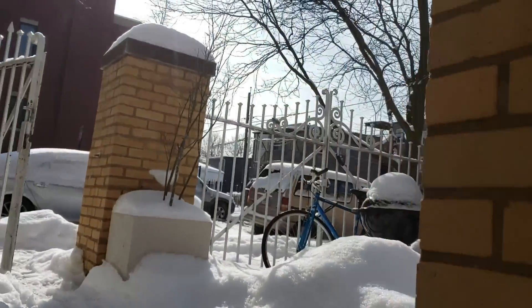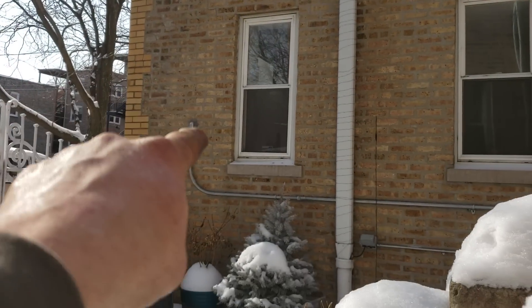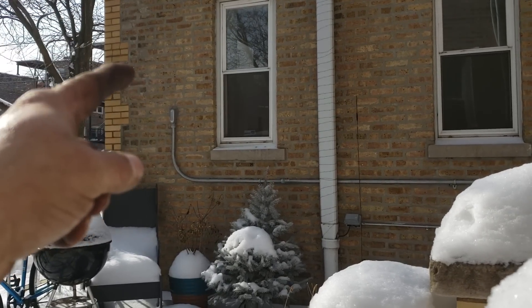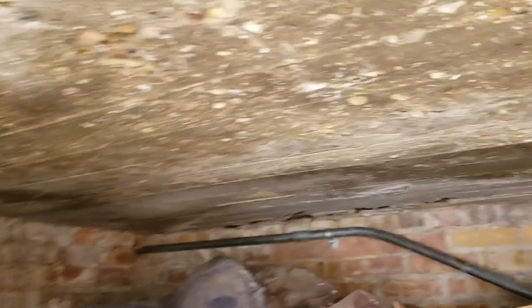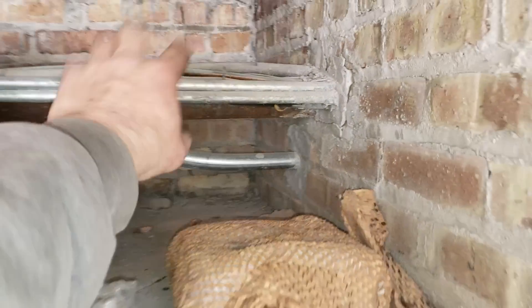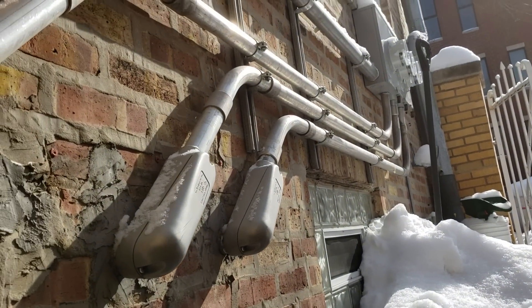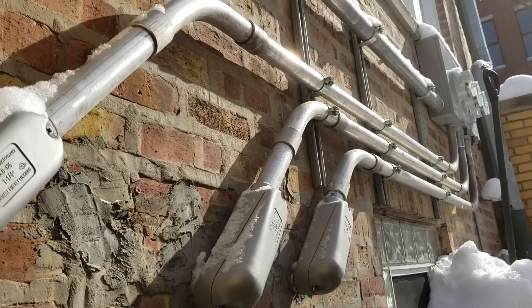They have a coach house here, which was fed overhead to over there. And then there's a panel right there, but that's illegal as fuck. So what I did was ran the pipe all the way through right there and then offset that. These junker pipes are from the HVAC guy, before I ever even got here. So I put in a clean service, and I told the guy, this is the start — it's not going to fix everything in your building.